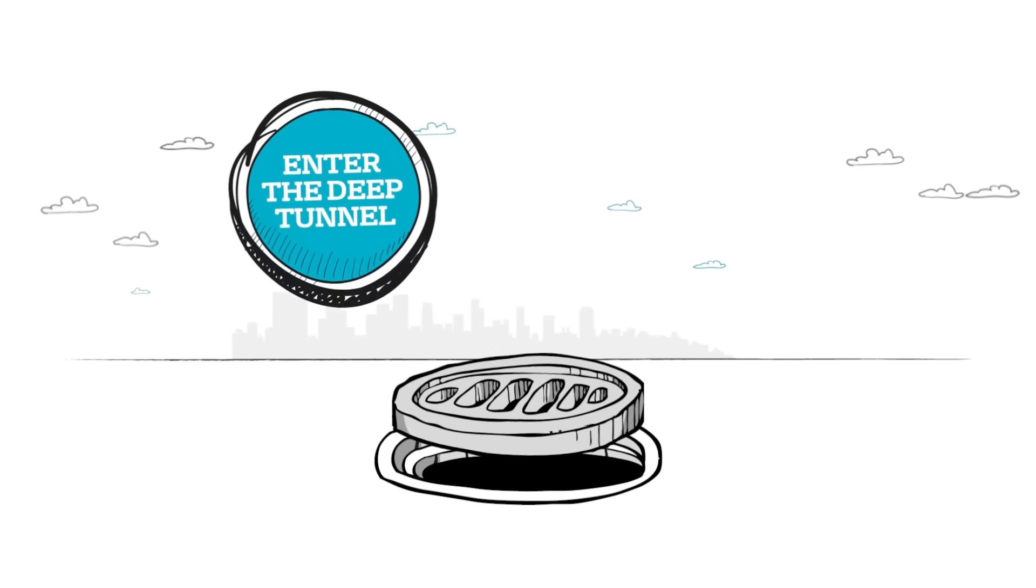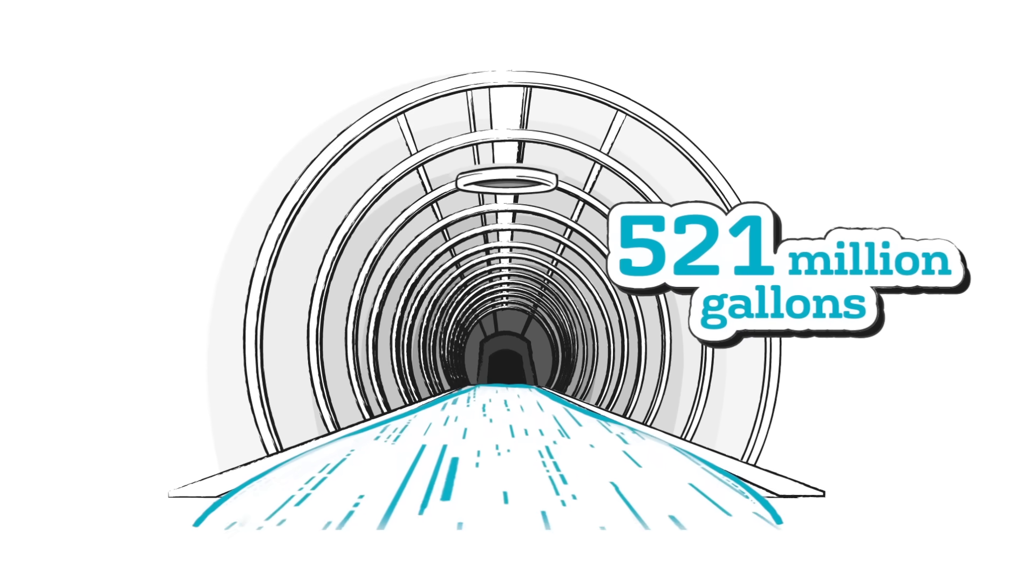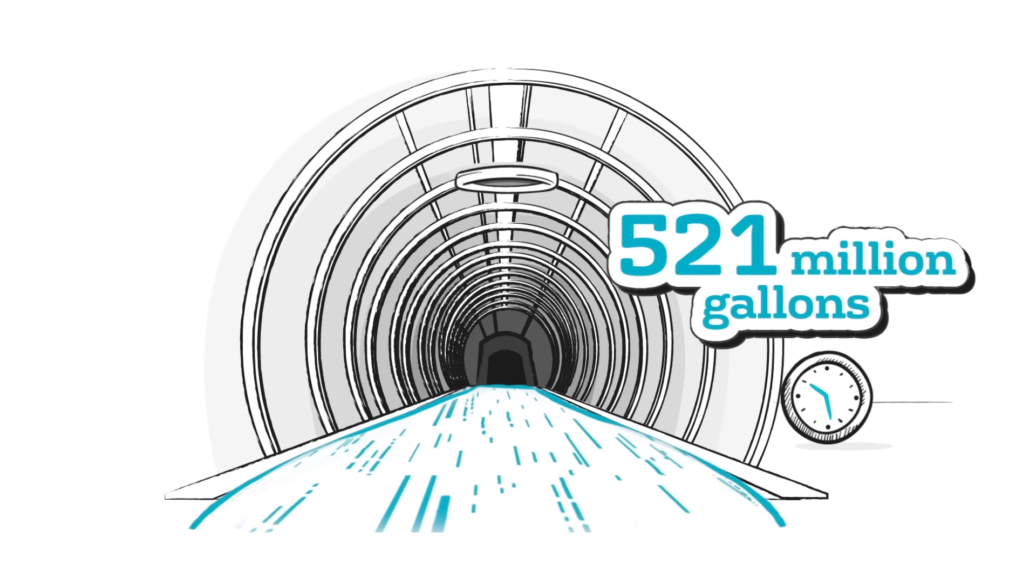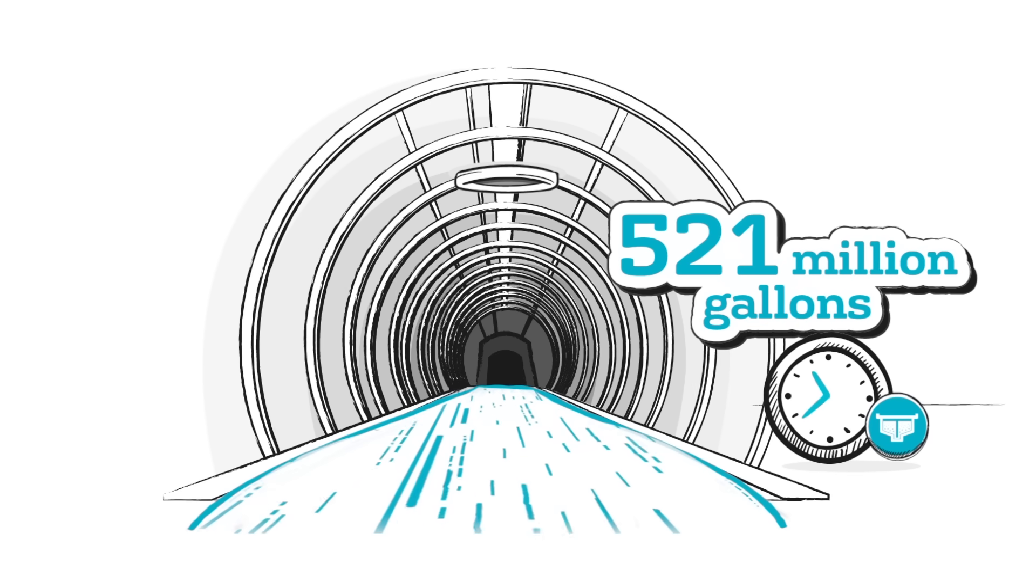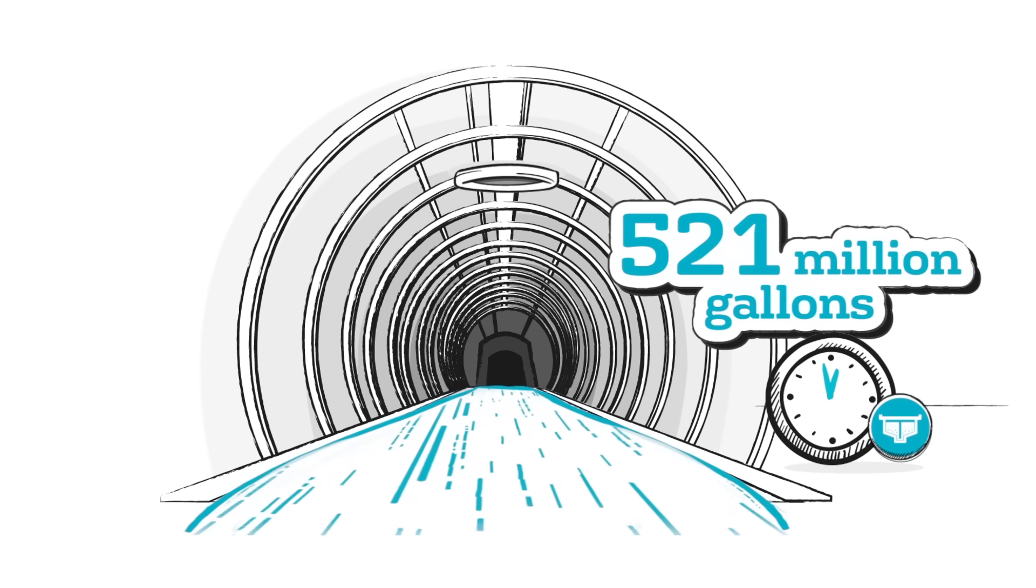Enter the deep tunnel. It has the capacity to store up to 521 million gallons using 29 miles of underground tunnels buried 300 feet deep, until it's able to be treated later on using three 5,500 horsepower pumps.